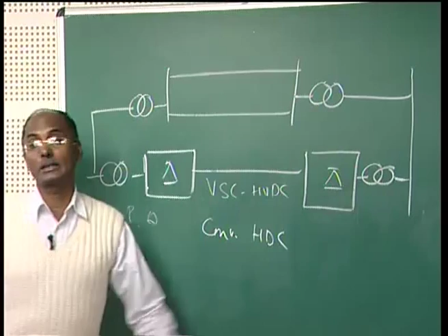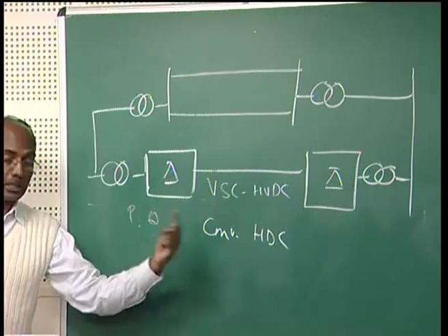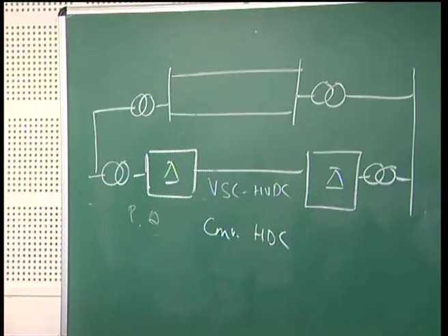Another advantage of the HVDC light DC cable is that it has a low magnetic field. How? The magnetic field is reduced by laying the HVDC light cables with anti-parallel DC currents — the outgoing and incoming currents are placed together, so the resulting magnetic field decreases with distance from the cable.